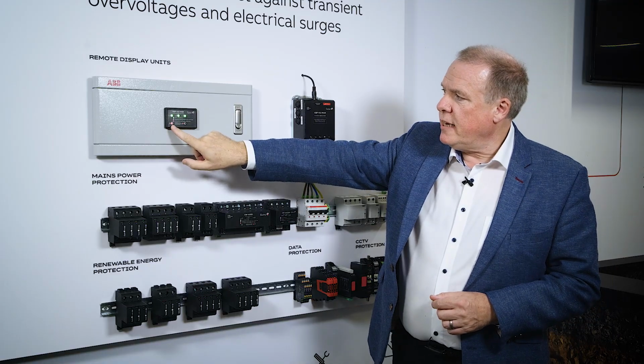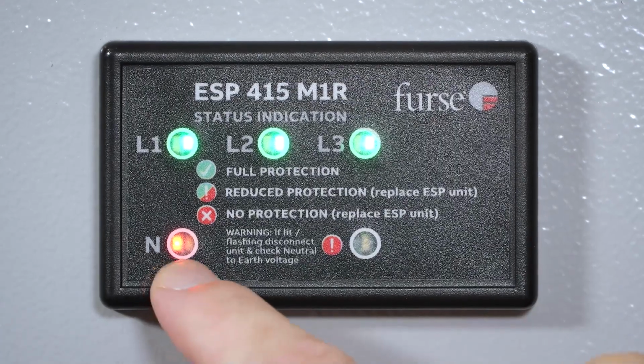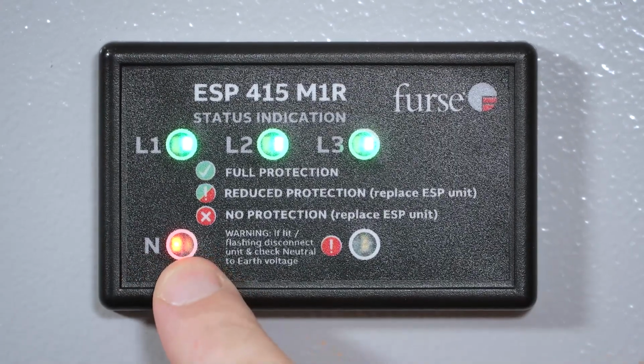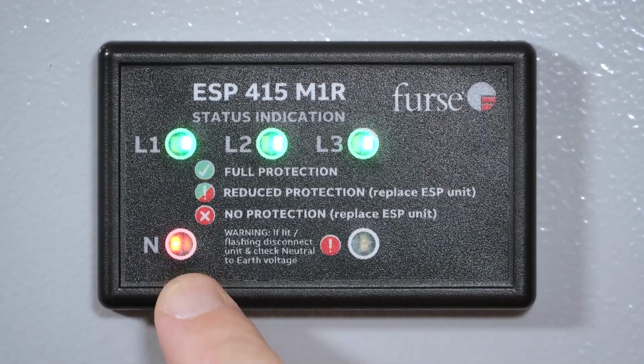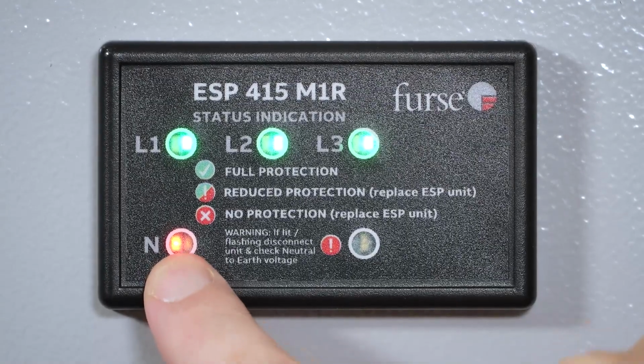On this one, you can see the neutral is now red. You've lost protection on the neutral or the earth line. This is now needing instant replacement of the SPD.